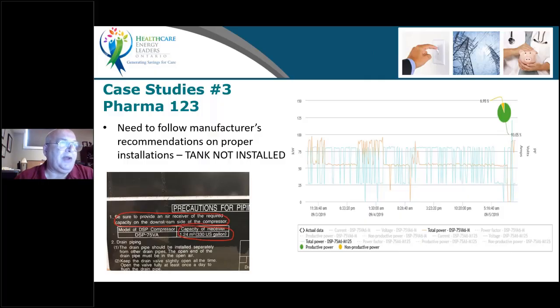And we can see that by the power graph chart, that both compressors are basically fighting each other as they're loading and unloading, or one's loading, and so on. Orange and blue are the two 100 horsepower. So improper storage and incorrect piping had two compressors on all the time, simply fighting each other because of the back pressure created. And I believe they've increased their pipe size to a common header, installed a tank, and they're good to go.